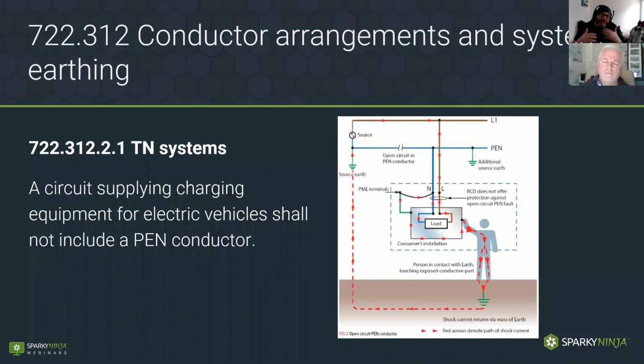So what we've done in the previous circumstances, though, is we've just converted things to TT systems, in caravan parks and things like that. That's fine. There have obviously been questions about the safety of that with electric vehicles, because the electrodes go down much closer in the home to underground pipe work and your PME cable. So we'll see in a minute where the regulations don't quite like that idea of always converting PME to TT systems in section 722. But all of this issue, this PEN conductor, has created the requirement for protection, and it's something they've been redeveloping technology for over the past few years, and it's had to create a little bit of a rewrite in this.